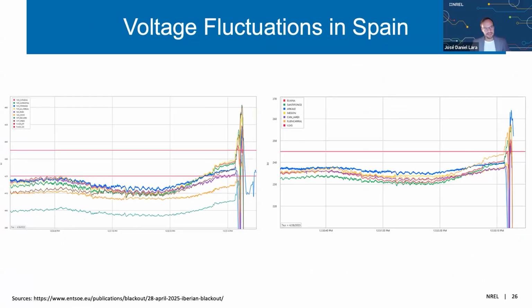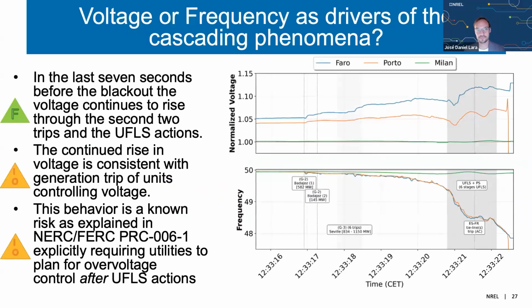So again, let's do a quick review of what we've learned so far. The system was experiencing high voltage fluctuations and oscillations. We have an oscillation of a plant that latches onto this voltage fluctuation. Then we have an oscillation with the rest of Europe. The operator tries to dampen that oscillation following protocols. Those protocols just worsen a voltage situation that was happening hours before the blackout. And then we have a runaway of voltage that starts tripping units and losing frequency and increasing even more the voltage.